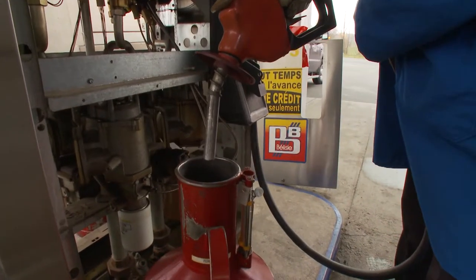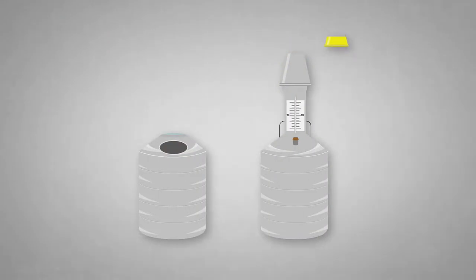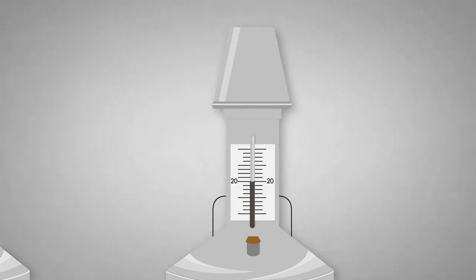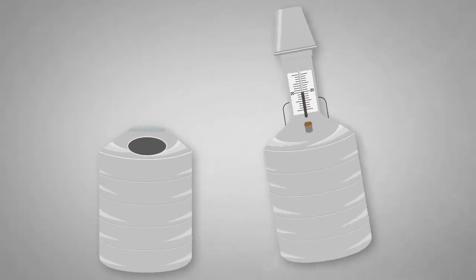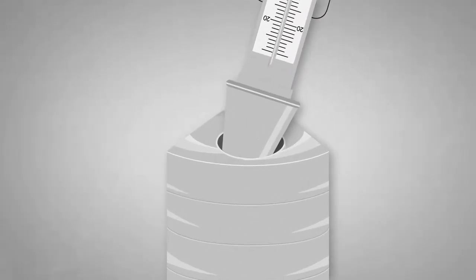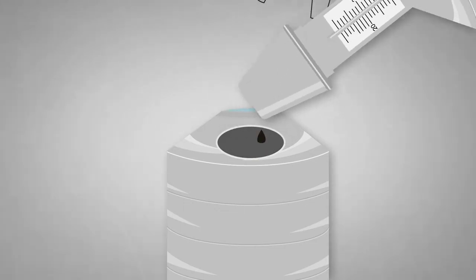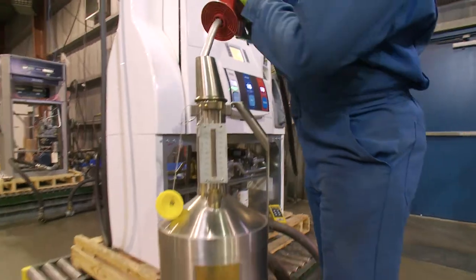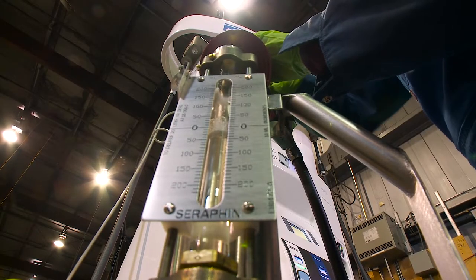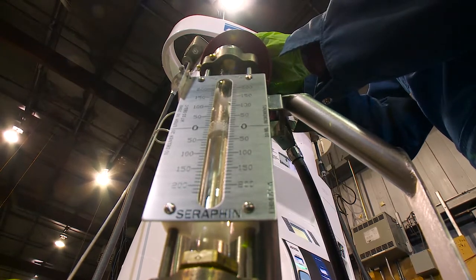The standard must now be wet down. As discussed earlier, the standard is calibrated to deliver, and when it is filled to its nominal capacity, the amount that can be drained from the standard is the nominal capacity. Wetting the standard eliminates the loss that would occur from test liquid clinging to the dry internal surface. The wetting procedure is as follows. 1. Fill the measure to its nominal capacity with the liquid to be used to perform the inspection. 2.